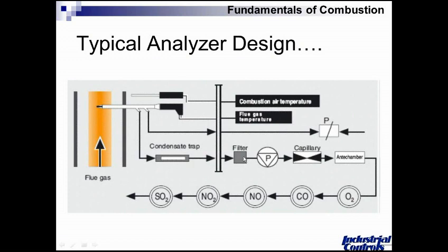As we learned in earlier slides, one of the byproducts of good combustion is moisture. So we take the moisture out of that sample. There might be some particulate involved, so we pass it through a filter. The P here in the diamond is our pump.